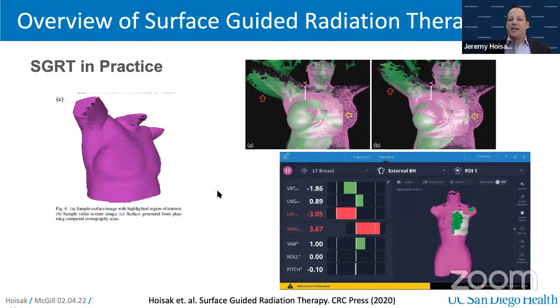So I had mentioned that we use the CT body contour, which is obtained at CT simulation. This serves as a reference. This is exported to the SGRT system, and then it can be loaded up in users' control system shown here on the right. The patient will then get positioned on a treatment table, and then we will take a live image of their surface. So in here in magenta is the CT or the reference surface, and in green is what the SGRT system is actually imaging.